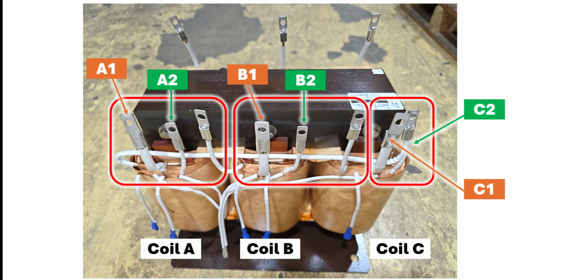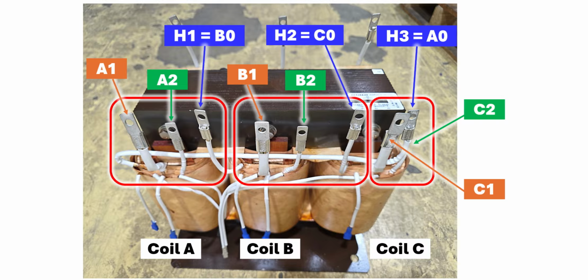After taking required safety steps and gaining access to the connections, let's look at the connections that we need to work with. There are 3 leads out of the primary side of each coil on transformer T1. The transformer taps H1, H2, and H3, which connect to the AC input circuit breaker, are determined by the 0 wire of each coil. H1 equals B0, H2 equals C0, and H3 equals A0. The voltage, either an A value or a B value, is determined by which of the remaining 2 wires, number 1 or number 2, is connected to H1, H2, and H3.